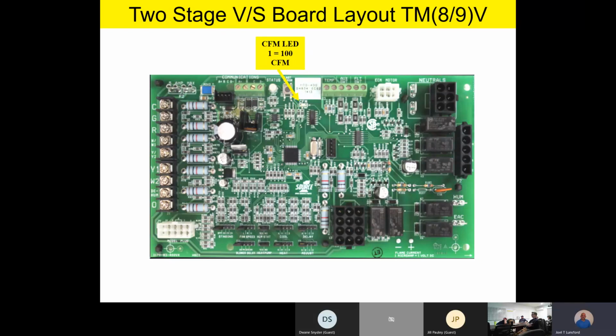We have a CFM LED. Now this is kind of a cool little thing too, in the fact that the variable speed products, we're going to provide you with a CFM LED. Now that CFM light will flash one time for every 100 CFM that's programmed on the board. So in other words, it doesn't matter if it's in the heating mode, it doesn't matter if it's in the cooling mode of operation, doesn't matter if it's first stage, second stage, doesn't matter. Whatever CFM is programmed on the board, that indoor blower, because it's a variable speed motor, is going to ramp up and down to meet that CFM that you have programmed on the board with your jumpers, which we'll talk about in a little bit.